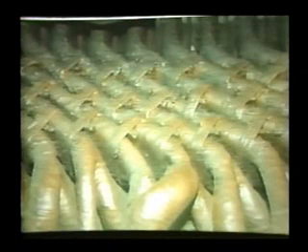Just take a practical example and consider what we see in the next couple of slides here. Here are the end turns of an actual winding on a large machine in the 5,000 horsepower range. And note that each coil has 3 ties, 3 rows of blocks and ties, and obviously we're looking at the bore side of the coil here. And on the back side, the coils were tied to a ring, and there were 2 additional rows of blocks and ties. This was on the original winding.